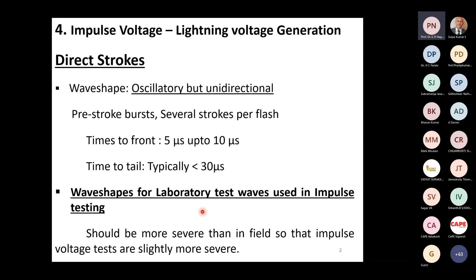Then why do we use shorter times to front and longer times to tail is a big question. Now, the test wave shapes used in the laboratory, this is the most important consideration. This test wave should be more severe on the test object than in the field. The most common and most critical test objects in the lightning test are the power transformers, the high voltage, high power transformers, because they face lightning very often, and if the transformer fails, millions of users of power can be affected. Therefore, that's the most critical component of the power system, and that defines how the lightning wave shape is defined for testing of the power transformers, and therefore for practically all other equipment.